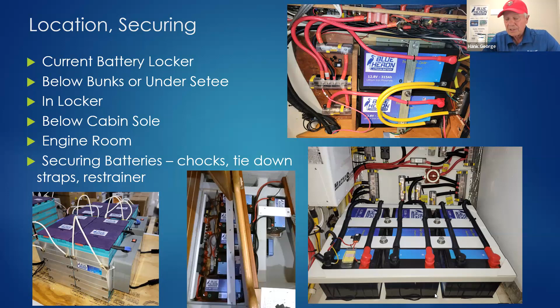Another key aspect with lithium batteries is securing them. You'll see pictures with clamping plates over the top and threaded rods to an anchor. With lithium, you want to hold the battery firmly in place. ABYC standards for AGM and lead acid allow the battery to slide a nominal amount, like an inch, but no more. That creates impact loading with lithium, so you want to avoid it. The plates in a lithium battery are paper thin, built up with separators between them, and suspended from the top and bottom of the cell case, so you don't want lateral loading from sliding around. You generally use blocking or chocks at the base to hold them securely, then clamp it down so it's not going anywhere.